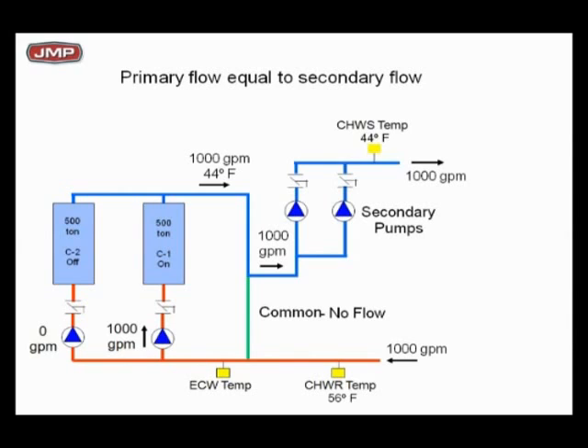So my first chiller sees a return water temperature of what? 56 degrees. So chiller 1 is fully loaded, 12 degree delta T, producing 500 tons, return at 56, supplies 44. A perfect world, fantastic world. The primary flow rate is exactly equal to the secondary flow rate, and there's no flow in the common. You won't see that very often, but that's a possibility you need to understand.